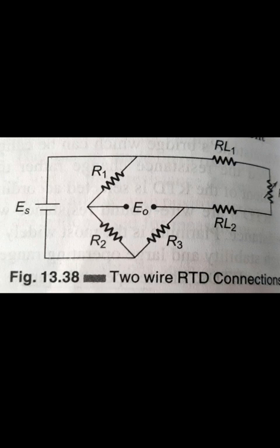Whereas the resistance temperature detector, that means the RTD, commonly uses platinum, nickel or any resistance wire whose resistance varies with the temperature and which has high intrinsic accuracy. They are available in many configurations and sizes as well as shielded and open units, for both immersion and surface applications. The relationship between the temperature and resistance of the conductors in the temperature range near 0 degrees Celsius can be calculated using the equation.